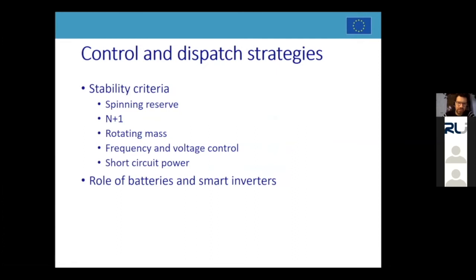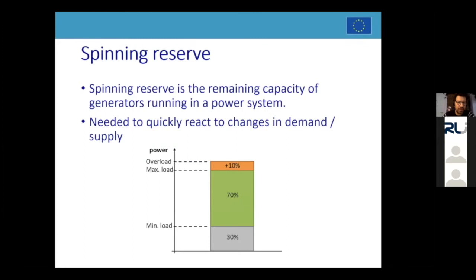So here is an overview about stability criteria. In your island energy system, you usually make sure that you have enough spinning reserve. You follow an N+1 rule, rotating mass for frequency and voltage control and short circuit power. And let me explain spinning reserve. Spinning reserve is the remaining capacity of generators running in a power system, which is needed to quickly react to changes in demand or supply.